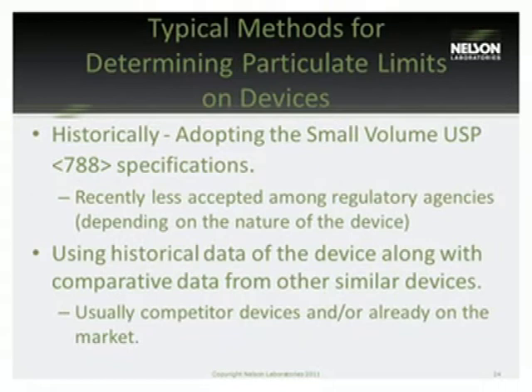Some typical methods for determining particulate matter on devices. Historically, the small volume USP 788 specifications have been used, and the method in that standard referenced for testing of devices. However, in the last couple of years, this method of adopting the 788 to devices has been less accepted by most regulatory agencies, including the FDA. It does depend on the nature of the device. In some cases, implantables or smaller, less invasive devices may still be adequate to be tested to the 788 specification, but in most cases, it's recommended to come up with a custom protocol and not to rely on 788 for testing of a device.